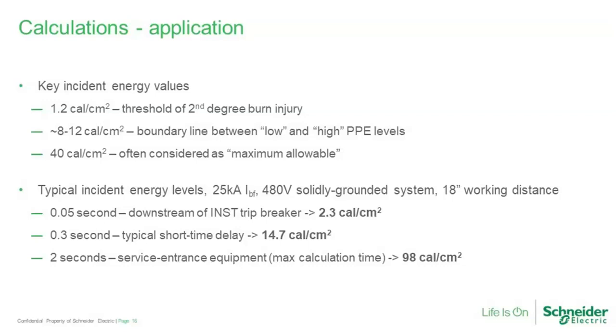40 calories per centimeter squared is another magic number that's thrown out there sometimes. A lot of organizations, Schneider Electric included, look at this as sort of the maximum allowable. We won't allow our folks to be exposed to energy levels above 40 calories per centimeter squared. So, that's a lot more than 1.2. Do we really get there in real systems?